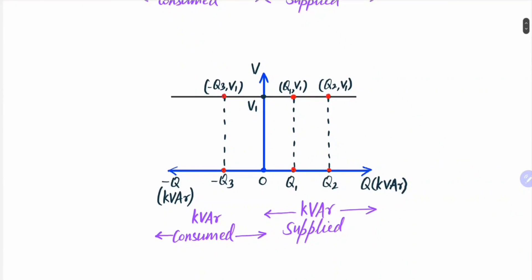Similarly, the vq characteristic of an infinite bus bar is shown in figure, where v is terminal voltage and q is reactive power. Here also we can observe that whether the reactive power supplied by the infinite bus bar is q1, q2, or any other value, the terminal voltage remains fixed as v1, where v1 is terminal voltage at no load. Even if reactive power is being consumed by the infinite bus bar, the terminal voltage remains fixed.